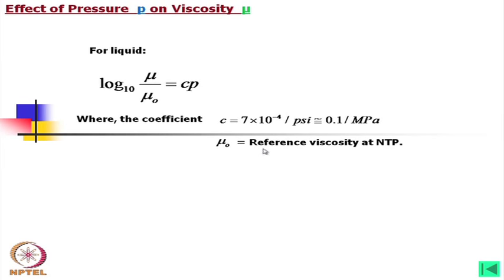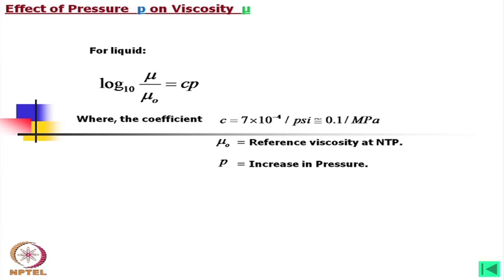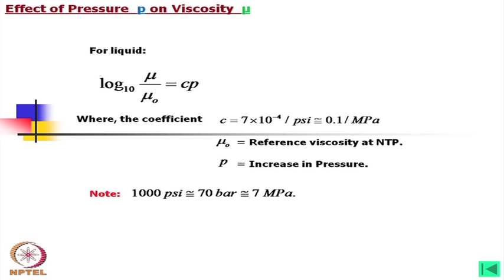Here p is the increased pressure. A useful tip: in many cases pressure is expressed in bar or psi. To convert to megapascals, for a fluid power engineer it is very important to remember that 1000 psi is almost equal to 70 bar, which equals 7 megapascals, or 7×10⁶ pascals.